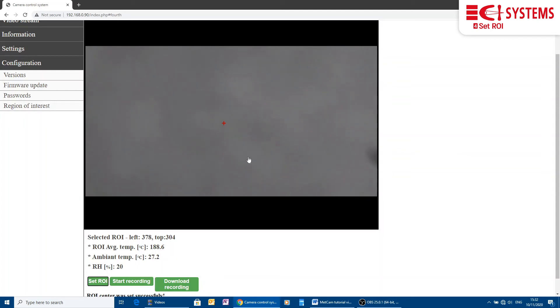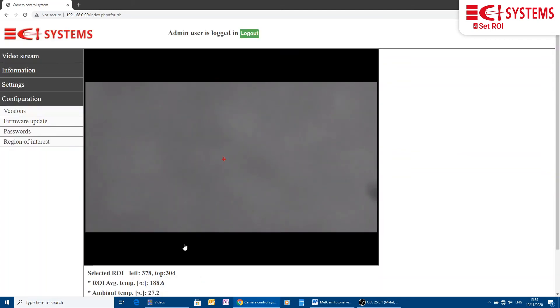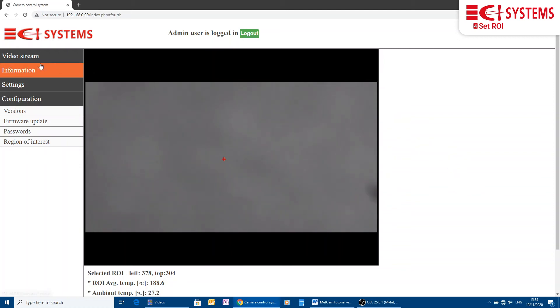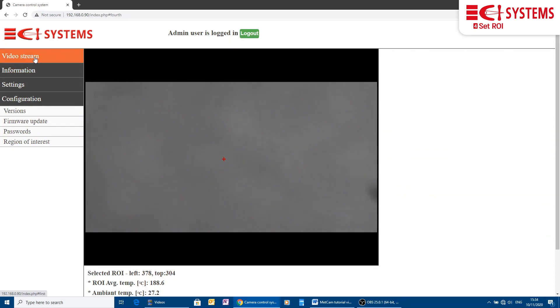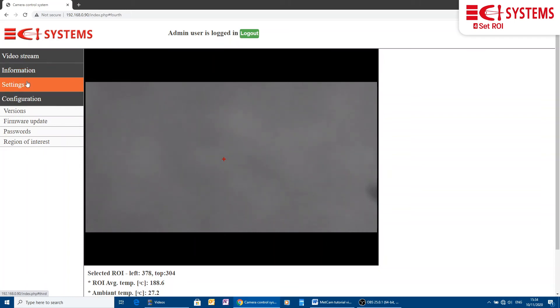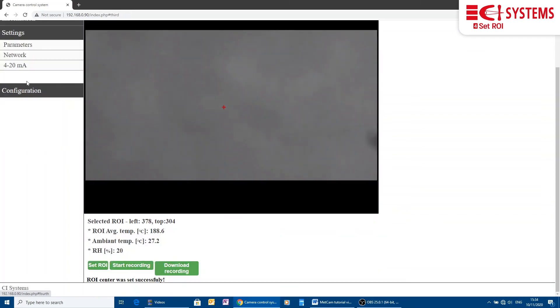Once the time, distance and region of interest have been set, METCAM starts monitoring. If gas is detected, it will issue alarms through the 4-20 mA interface just like any other gas detector.